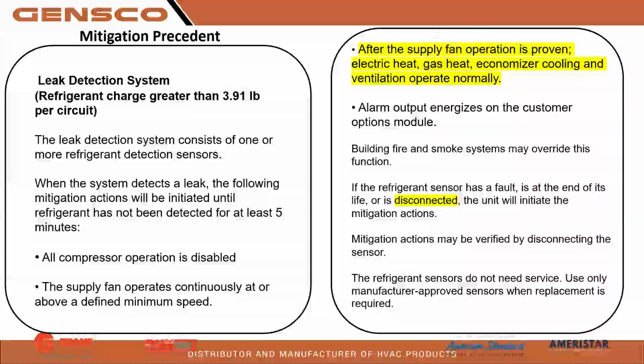Now this is important because Trane American Standard has thoroughly tested these under UL conditions to make sure that they did not ignite the 454B refrigerant. So Trane American Standard paid a lot for testing. They tested every unit and every heat strip combination, every gas heat exchanger. We do not reach ignition point for that refrigerant. So we are okay to operate gas and heat strip during a mitigation event.